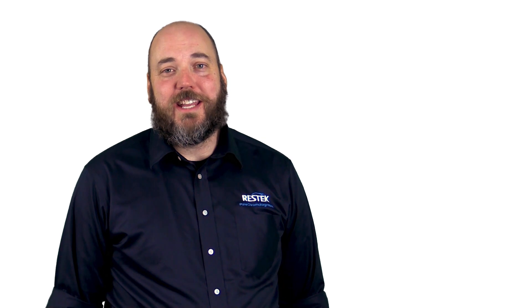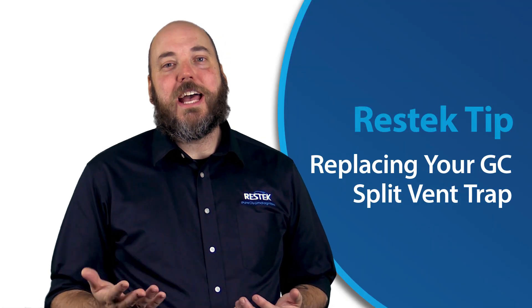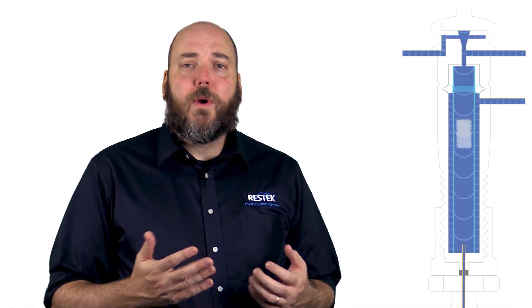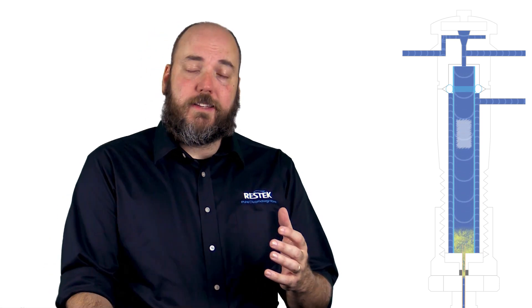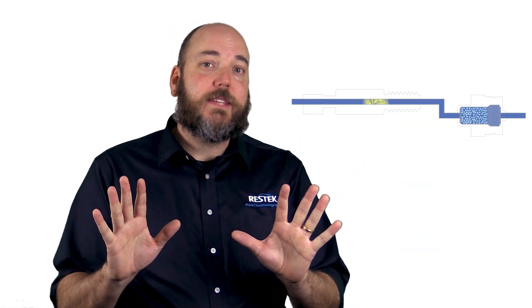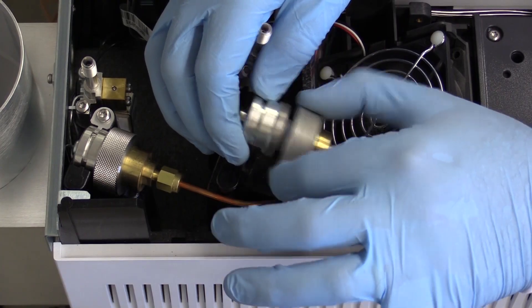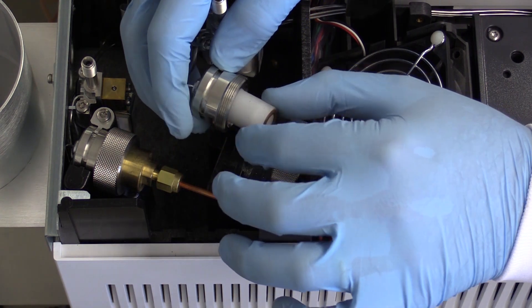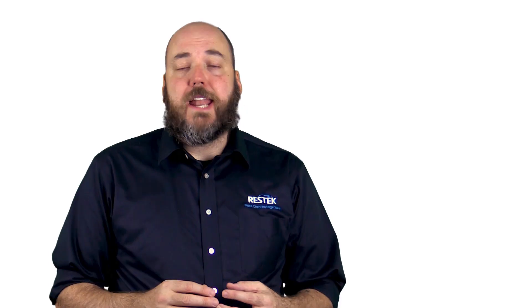Hi and welcome to this Restek Tip, where we'll be talking about split vent traps. In gas chromatography, instruments can operate in split mode, where your sample is simply split — some of it being directed onto the column for analysis, but most of it being sent out of the instrument. Instrument manufacturers have included something called the split vent trap, which is generally a small charcoal trap meant to scrub the contaminants out of that gas stream.